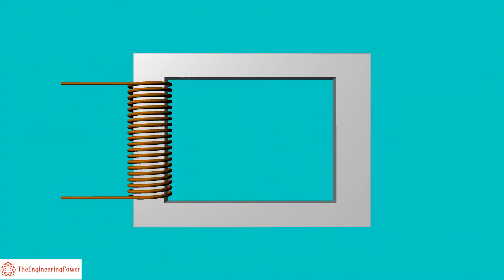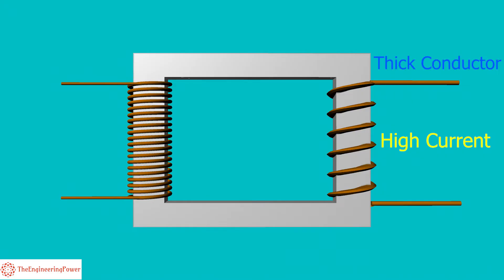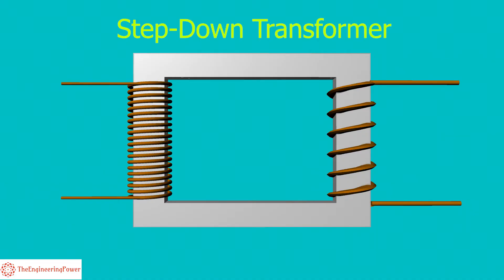Similarly secondary winding is also wrapped around the core. As there will be higher currents on the secondary side of PT because of low voltages, therefore thicker conductor is used in LV winding of PT. As the PT is a step-down transformer, so the number of turns in secondary winding are very less as compared to primary winding.